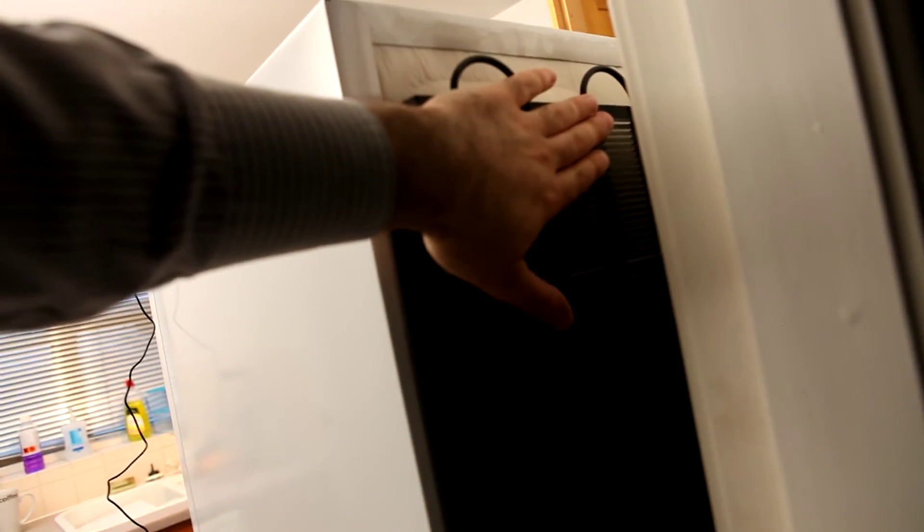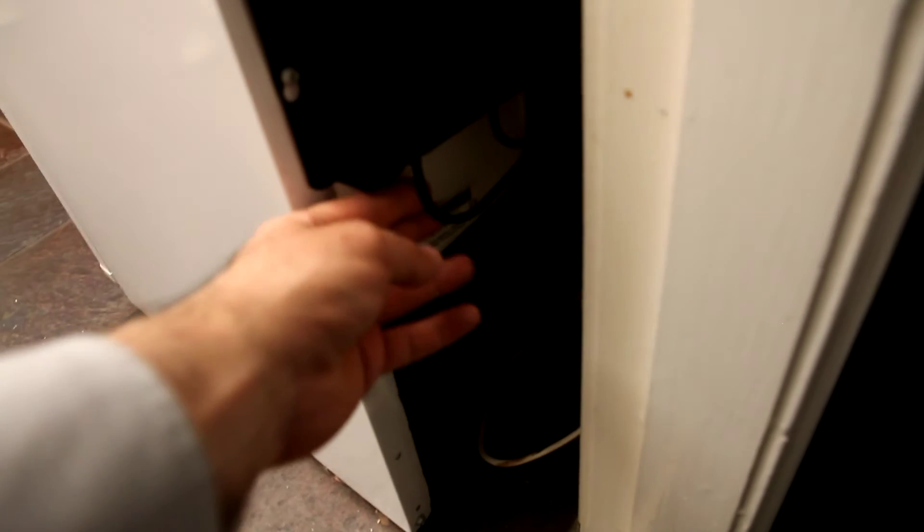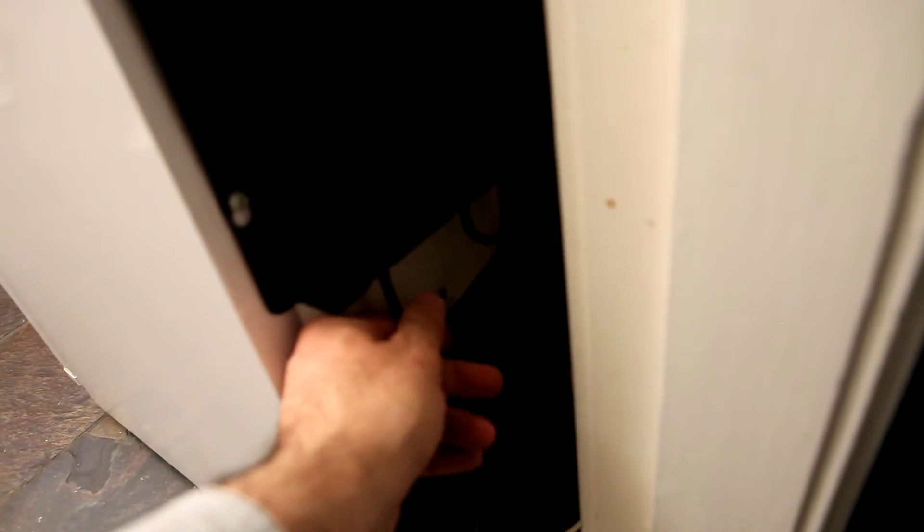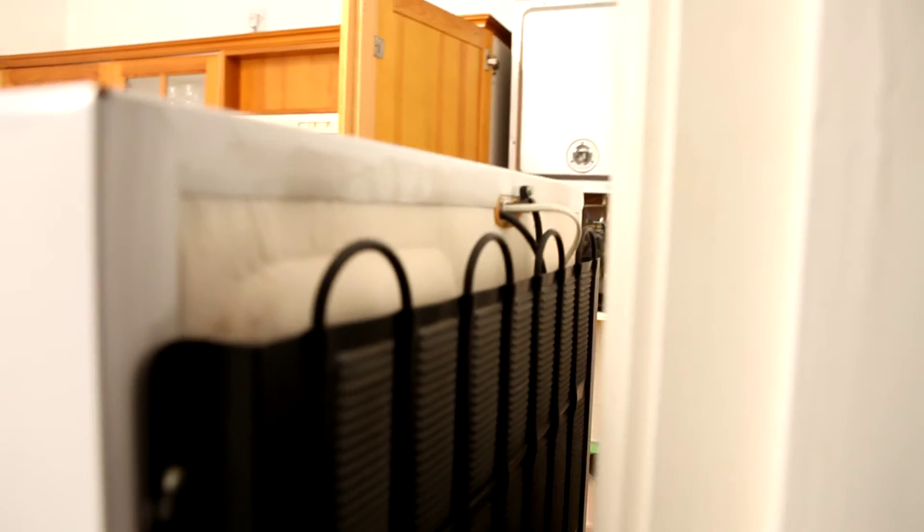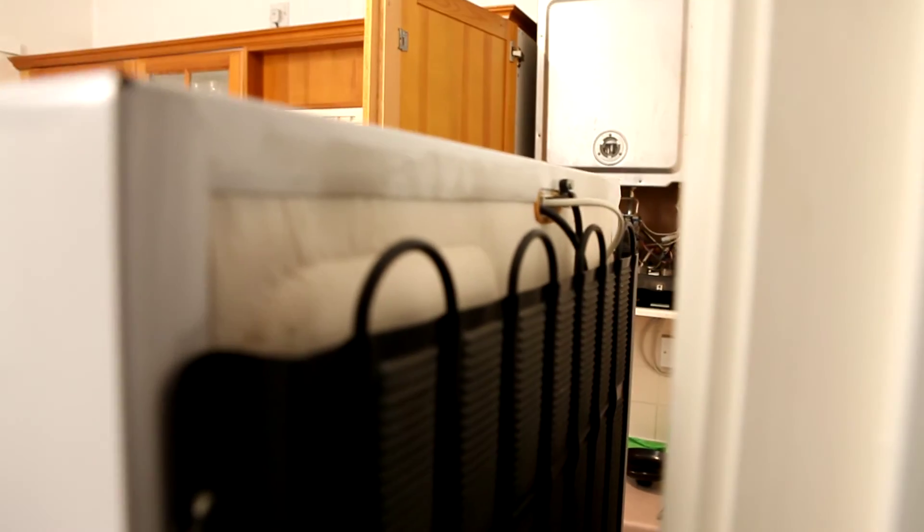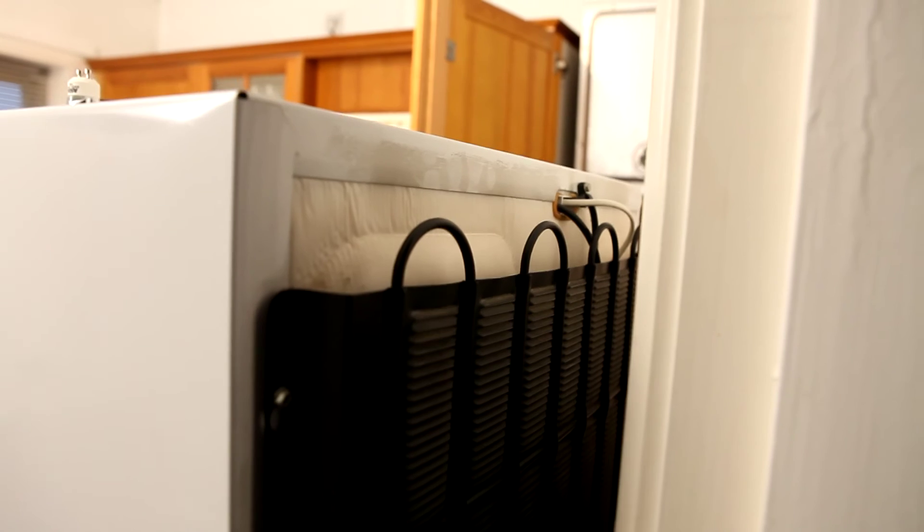And well, when you look at the condenser coils at the back, I mean, the compressor's running. I can feel it running. And these are just very, very lukewarm. And if we come down here, this is actually the discharge line from the compressor. And it's sort of body temperature. So there's obviously something badly wrong with it. I'm not an expert in refrigeration. I'm kind of guessing it's probably low on refrigerant. There's probably a crack or something in the line. But I'm hoping somebody who knows about refrigeration will be able to tell me what the matter with it is.